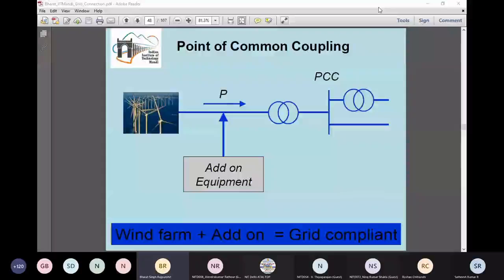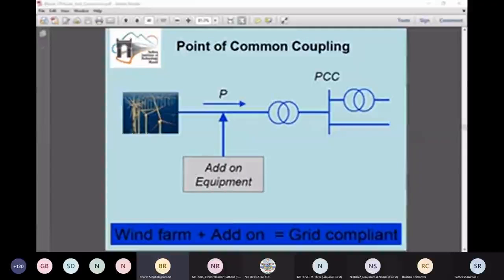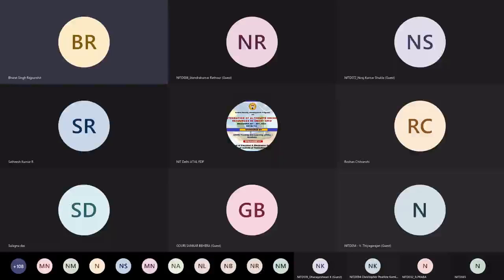It is something like a speed that we are deciding on. Let's say a car is there, we are putting our leg on the accelerator, pushing, so that we are maintaining a speed like 100 kilometers per hour. But if we see some obstacle, we reduce our set point, the reference point, so that our speed is reduced. So instead of 100 units of electricity we are generating and sending into the grid, we are now sending only 50 units into the grid. This is what I am saying. So this reference set point is always available with a controller or with a system operator. They should be able to reduce it. This is the requirement.